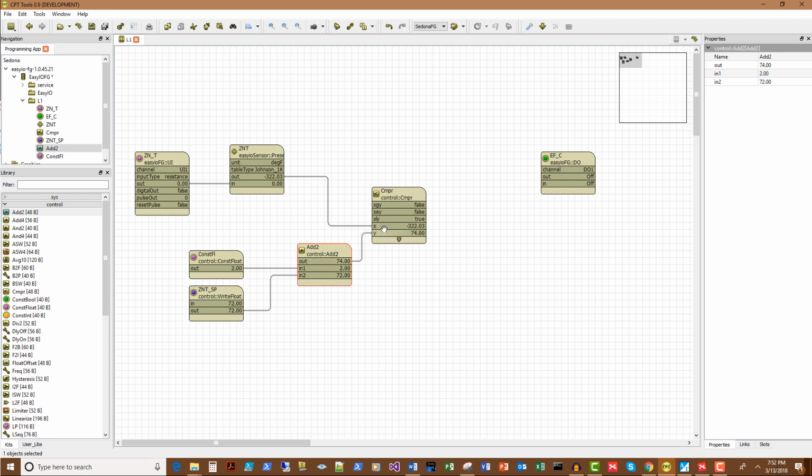And so now we have X, when X is greater than Y, plus that 2 degrees. So when temperature is greater than set point plus that 2 degrees, then we will have our output turn on. So you see, we can do that right there. Now you may be saying, but Phil, why is it not letting you drag this right here? Why are we not able to drag this comparator to this Boolean object? Well, you'll notice what's happening, right? You see me going out, out, out. That's something you need to be careful of, and something that you can get very, very frustrated with.